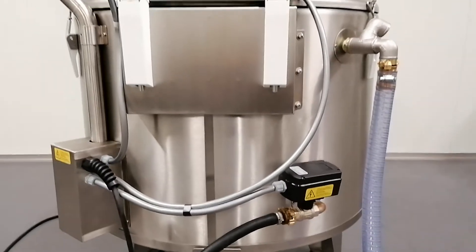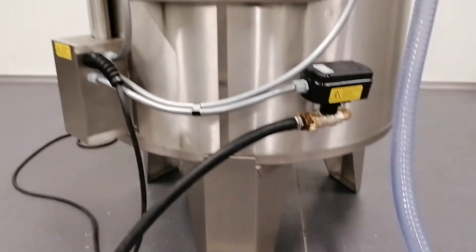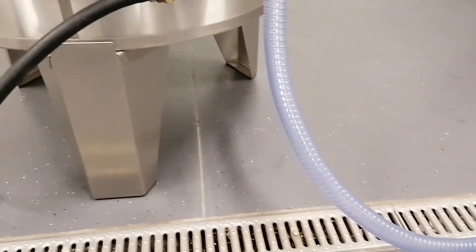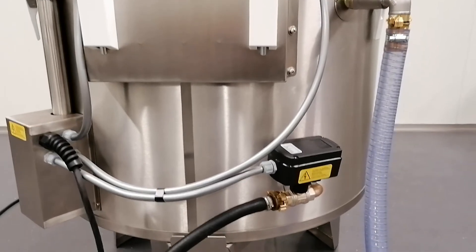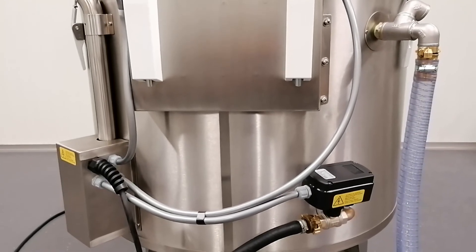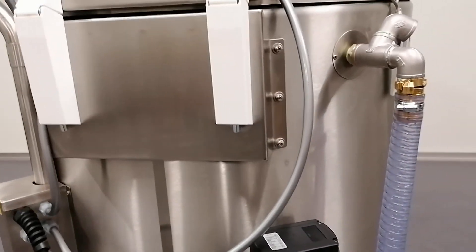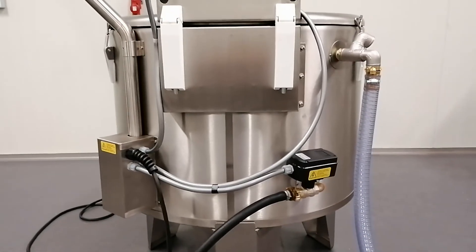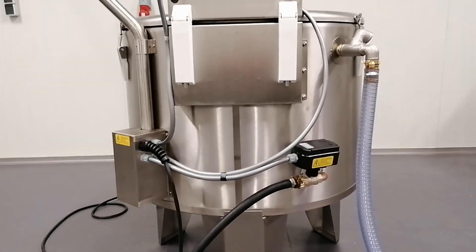And that was that. As you can see, no water came out of the overflow. What's important for draining is that there are no curbs in the draining hose and no height differences — you don't go down to the floor with the draining hose and then up again to some sort of drain, because that will cause the water to need pressure to push it over the curb, leading to water coming out of the overflow, which is not a sustainable situation. Once you have the draining hose in the right position, everything will be fine. I hope this is a little bit clear.